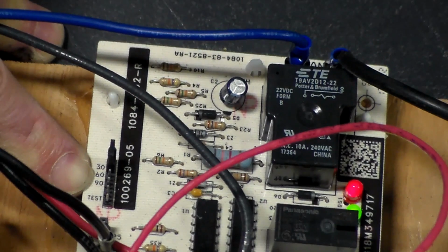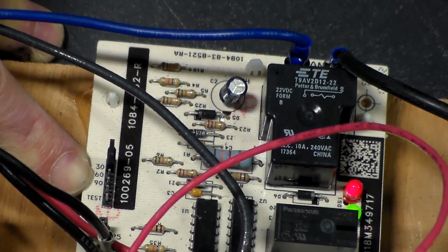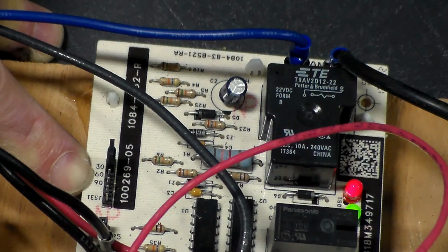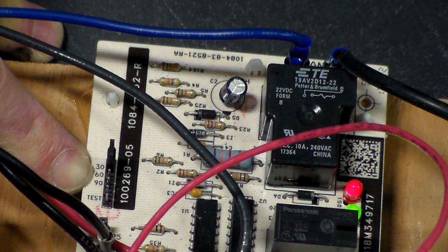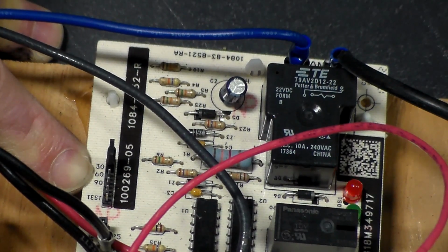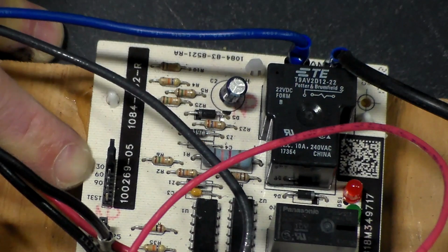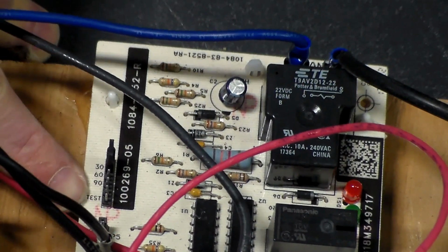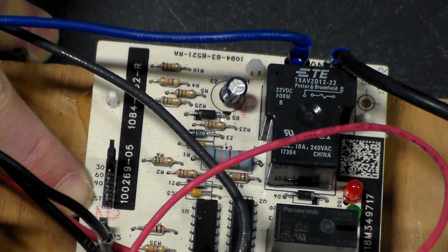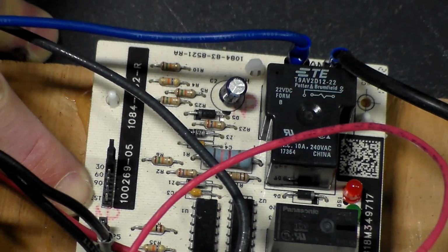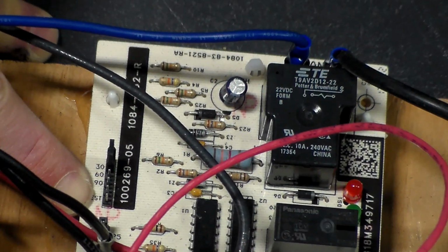Because if the defrost sensor reads open, like I said a second ago, it'll go into defrost for you, but then it's going to shift immediately right back out, and you won't be able to get any testing done or anything you're trying to do by testing defrost. So you have to first jump out the defrost sensor to trick the board into thinking that it needs to defrost, and then you move this jumper pin over and put it on the two test pins, and you just wait a couple of seconds and it'll shift into defrost for you. So I'll show you that in a minute. Let's zoom back out so we can look at the whole thing in action.